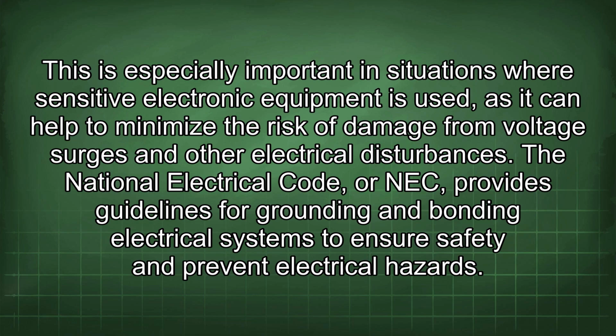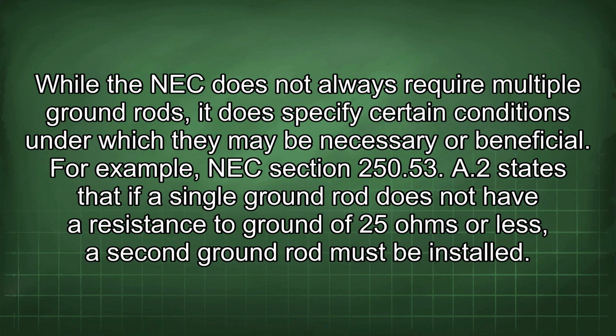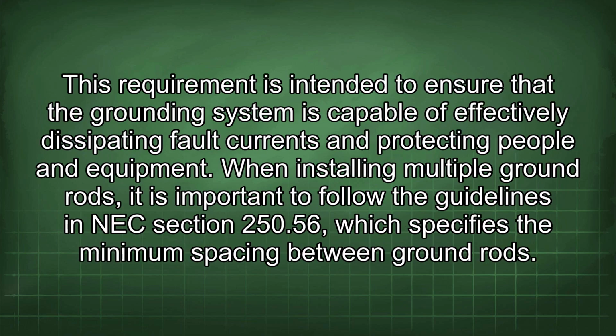The National Electrical Code, or NEC, provides guidelines for grounding and bonding electrical systems to ensure safety and prevent electrical hazard. While the NEC does not always require multiple ground rods, it does specify certain conditions under which they may be necessary or beneficial. For example, NEC section 250.53 A2 states that if a single ground rod does not have a resistance to ground of 25 ohms or less, a second ground rod must be installed. This requirement is intended to ensure that the grounding system is capable of effectively dissipating fault currents and protecting people and equipment.